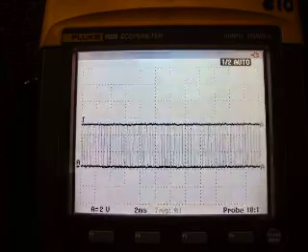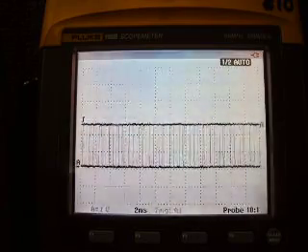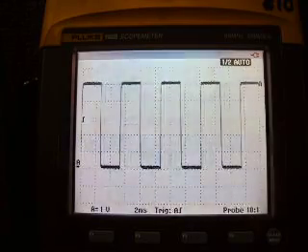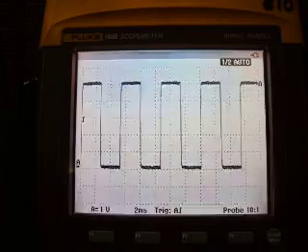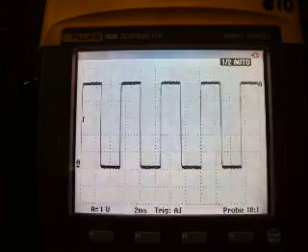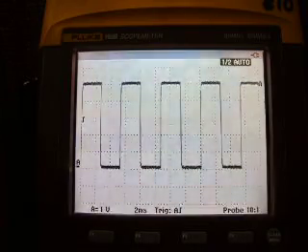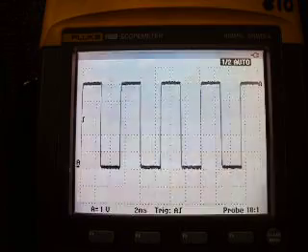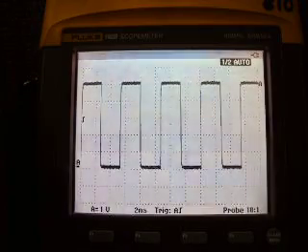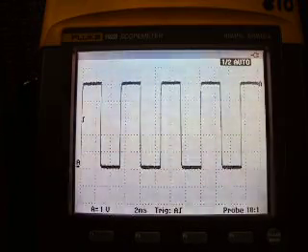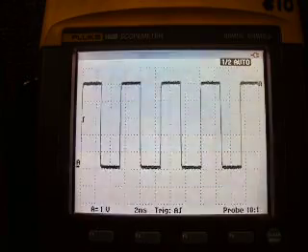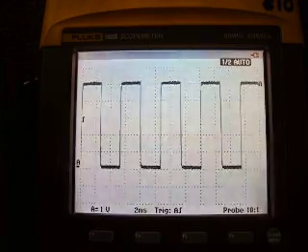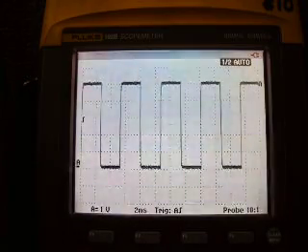But I think we'll just change our voltage reading back to where it was at one volt. So this will give you an idea of what you're seeing and how you need to use your time and your voltage and your trigger all in sync in order to get a nice picture of what you're trying to look at.